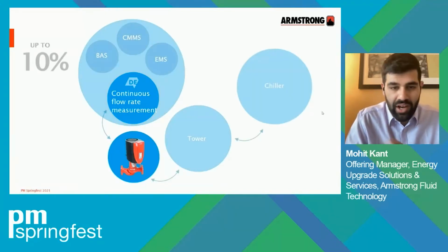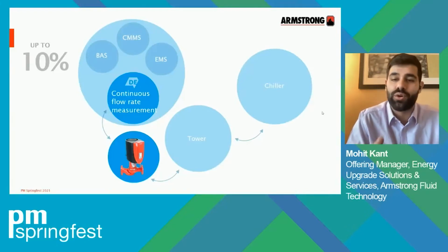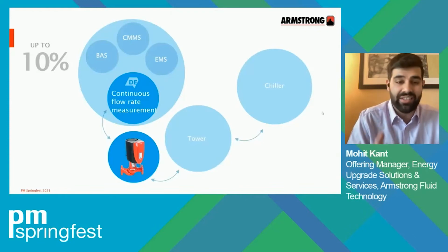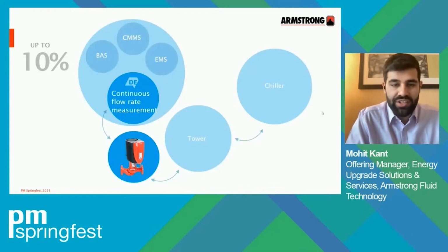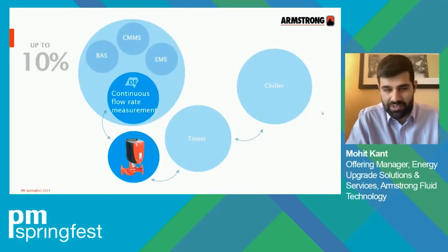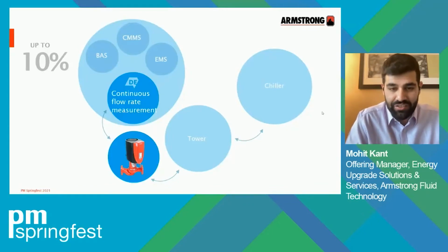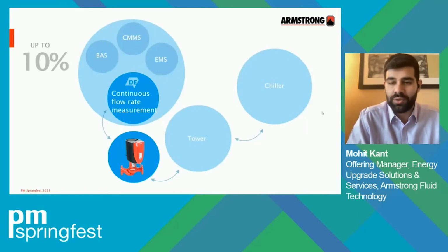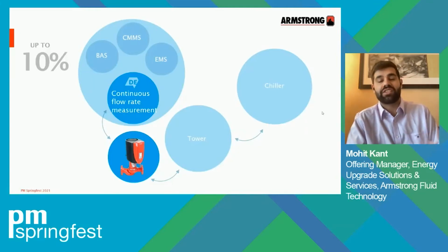By starting with an upgrade to intelligent pumps on the distribution side, we can get a much better understanding of the load, the building characteristics of the system and its components. It makes system operations transparent to the building automation system, the maintenance management system, and the energy management systems. And like a healthy heart, it leads and adds to the efficiency of other equipment in the system by ensuring the right flow rate, then to cooling towers and chillers. Most importantly, it can be a cash flow positive investment from day one, leading to up to 10% energy savings on the plant.